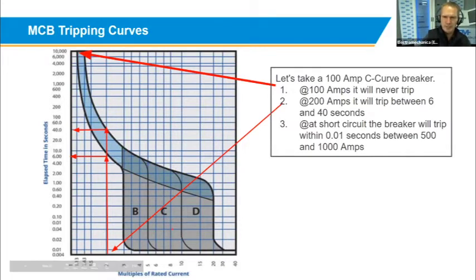So although the product might be rated at 10,000 amp on short circuit, this breaker will start opening between 500 to 1,000 amps. So again, if we go back to the scenario earlier about the motor starting or the motor running at 100 amps and that start up, even the C-curve product most probably will come out and see it as a short circuit and open and trip the circuit breaker, and the motor will obviously not run. So for motor applications, and depending on the startup currents, a D-curve is normally the preferred way to go for motor starting applications.